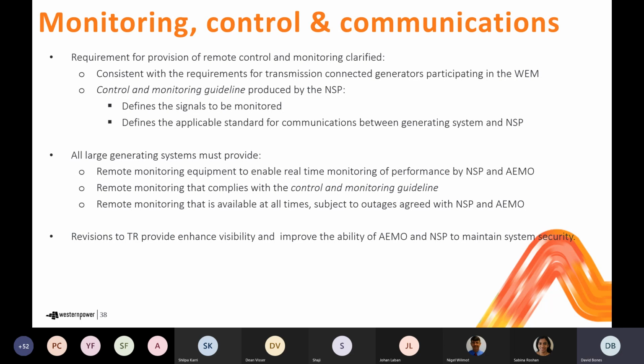Generally, the requirement is expressed such that all large generating systems must provide remote monitoring equipment to enable real-time monitoring of the performance of their facility by the network service provider and AEMO. That remote monitoring must comply with the control and monitoring guideline, and be made available at all times, subject to outages that have been agreed with the NSP and AEMO. So what this is doing is beefing up and making a bit clearer the exact requirements to ensure appropriate visibility and control of these large power systems.